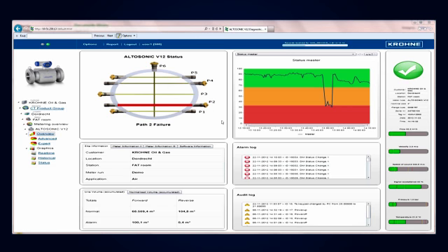There it is, we now get the full error on path 2. The meter is still custody transfer, as it uses path substitution, so the other paths compensate for the failure of path 2. However, there is a failure on path 2, indicating you should warn your maintenance crew.